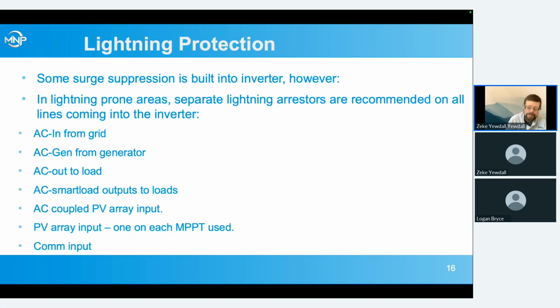And you add all this up, this is what? 1, 2, 3, 4, 5, 6, 7, 8, 9, possibly like 10 lightning arresters here, if we've got all these different lines coming in. But that's okay, they're about $100 each. If you've got this much stuff, this is probably a $30,000-$40,000 system. $1,000 to protect that from lightning is not that bad in the grand scope of things, and a lot better than trying to do an emergency lightning retrofit because it's gotten fried from lightning.